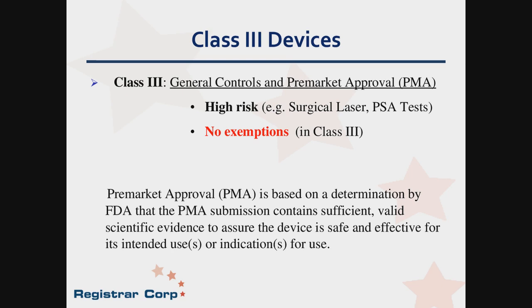The pre-market approval is really, how should I say, an extended 510K, because you also have to provide scientific data to the FDA that your device is safe and effective. Then FDA will look into it and really will approve these devices. A device might also fall into class 3 because you have a new technology, even if there are similar devices out there, but you changed the technology. So that could be a trigger that your device falls into class 3.